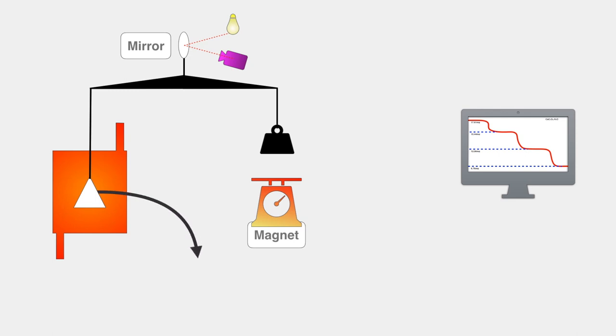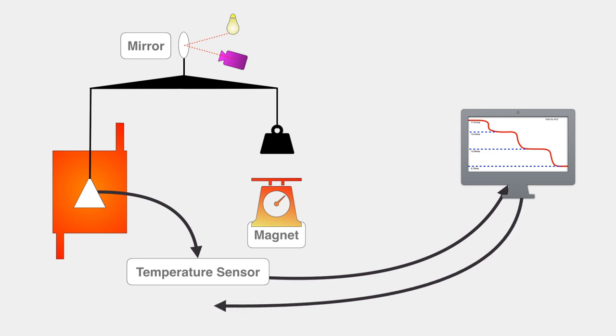So let's discuss working of this instrument. First of all, the temperature of the sample is sensed by the temperature sensor that is thermocouple. This temperature is sent to the computer and computer sends the information to the temperature controller to increase the temperature.